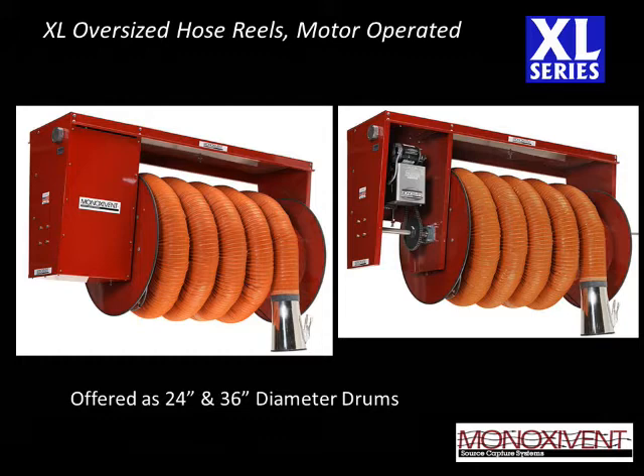An example application: we have these at military facilities where they bring in mechanics and train them how to maintain vehicles they'll see out in the field. This could involve very large pieces of equipment, like tanks or tube haulers, so very big hose reels for very big applications. In that particular case, we did 3,500 to 4,000 CFM for the 18-inch diameter hose, with somewhere between 6 and 7 inches of static pressure.